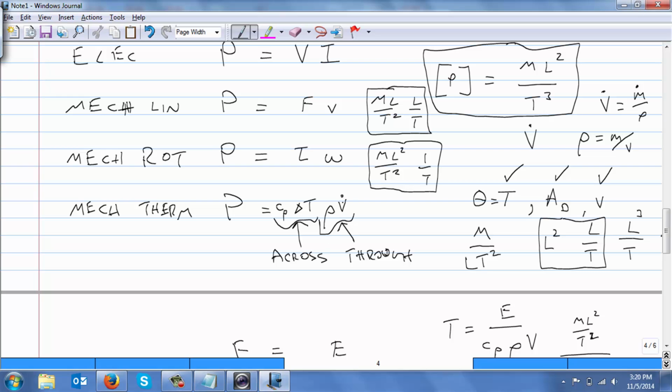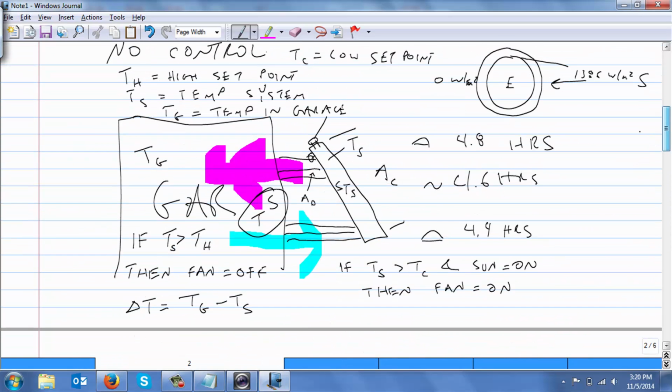And another way, obviously, is to push more mass through the thing, right? Just make the fan blow harder. But now, where's the limit there? I mean, why not say let's just blow it infinitely fast? Then it loses efficiency because it's not capturing the heat when it moves. If you just blow it through so quick, there's not enough time. The air does not spend enough time in the system to actually gather any heat. It's just flying through there.